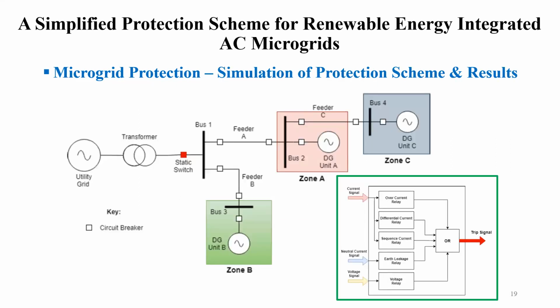So this is the single line diagram of the system which we have simulated in MATLAB, and we have used MATLAB Simulink with SimPowerSystems for the simulation. So we have a utility grid, that is our conventional main transmission system, or the NTDC's main transmission system. We have a transformer, we have a static switch or point of common coupling. We have a bus, and then we have feeders. This is feeder A, this is feeder B, this is feeder C, for zone A, zone B, zone C. So this is how our single line diagram looks.